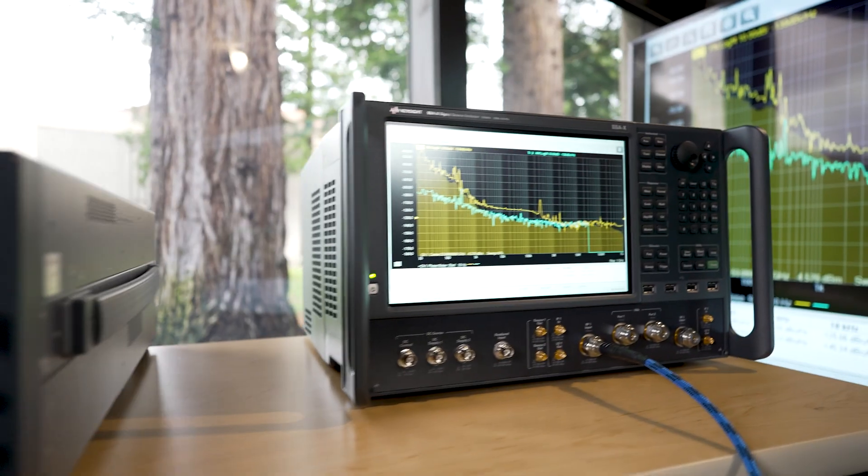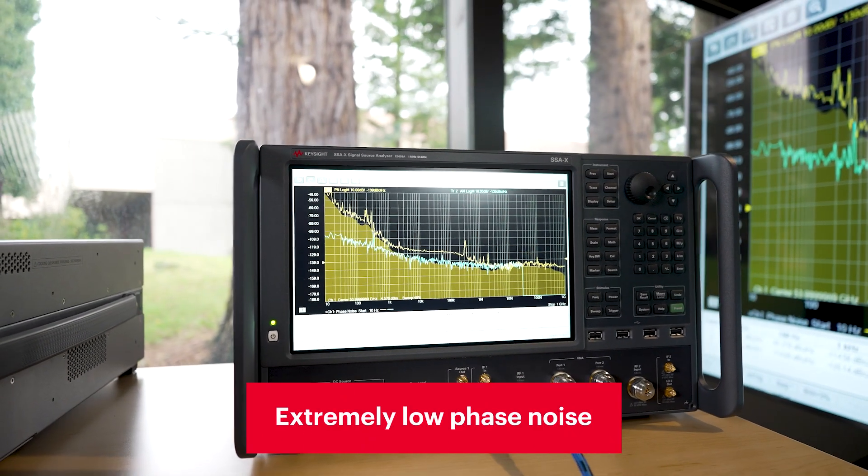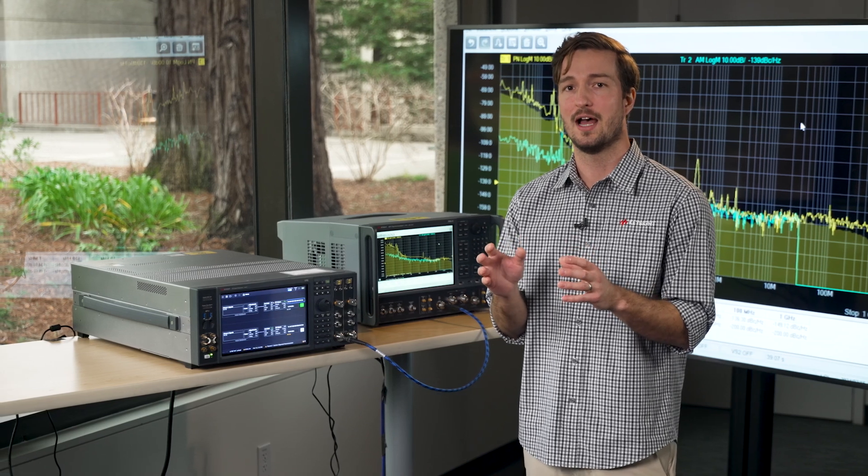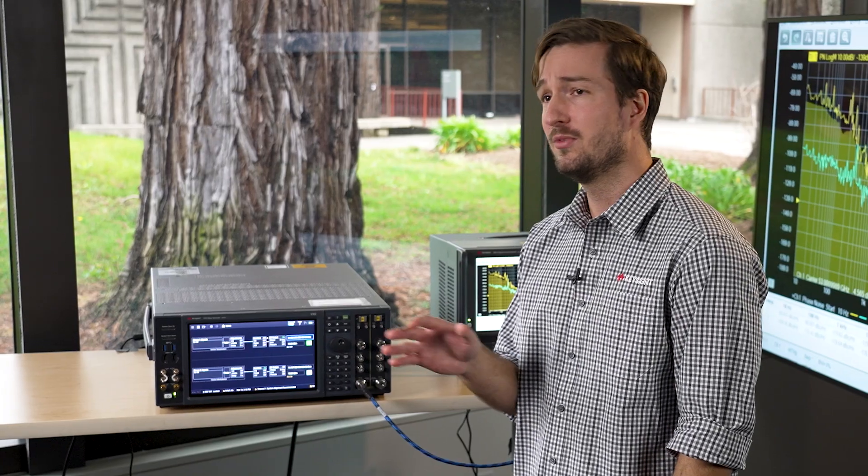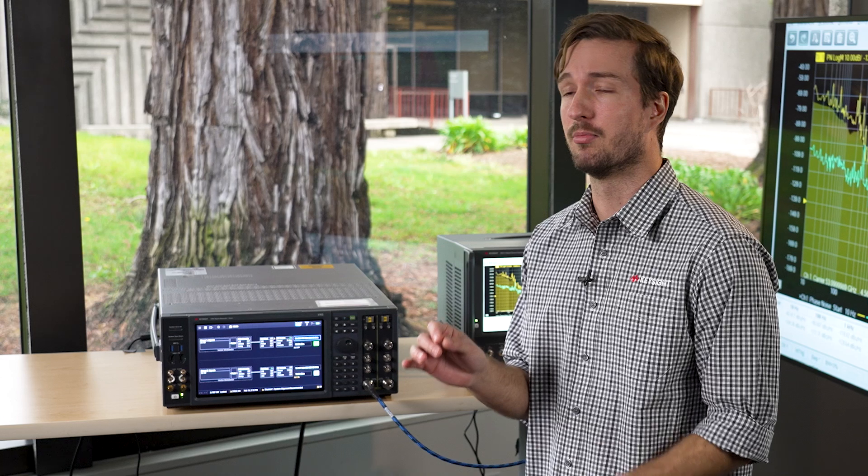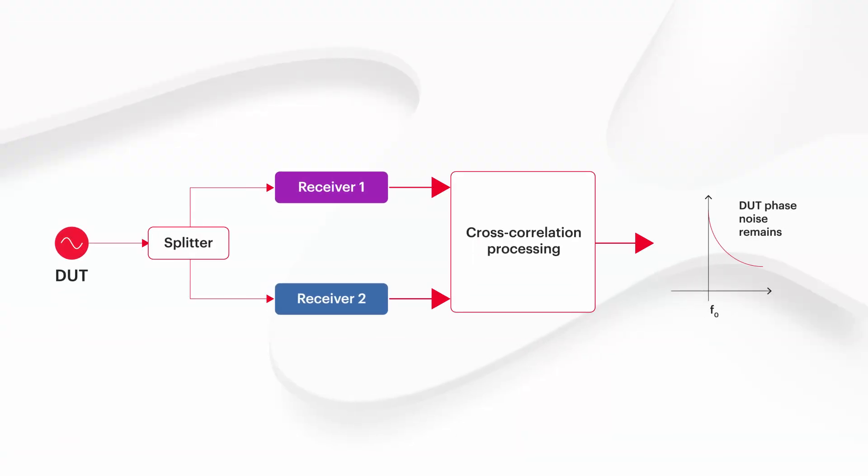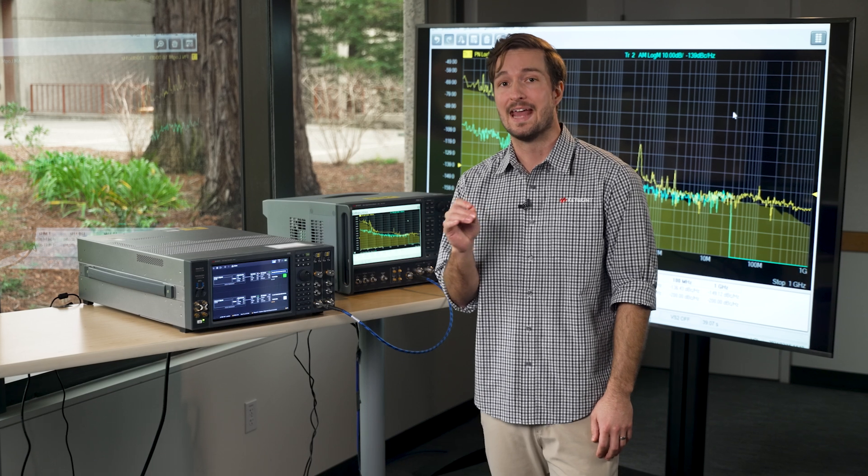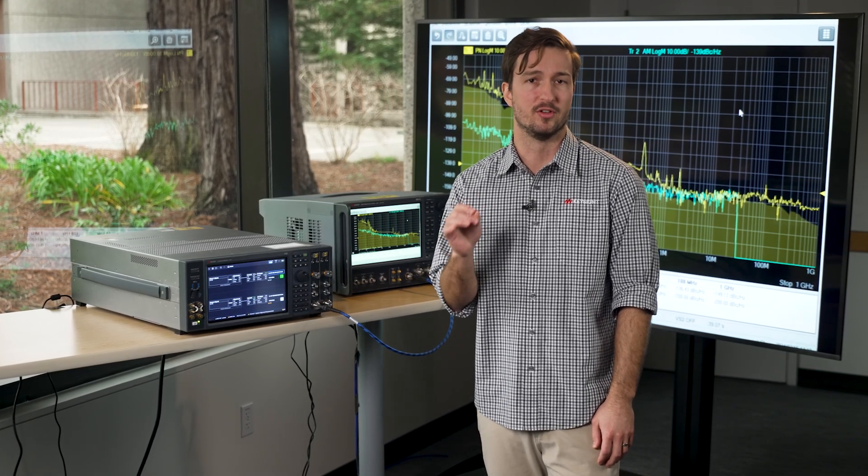The VXG has extremely low phase noise. In order to measure devices like the VXG, the SSA-X needs very high measurement sensitivity. This measurement sensitivity is achieved using a process called cross-correlation, where uncorrelated noise from two independent LOs and receivers is removed and the correlated noise from the DUT that is common to both receiver paths is retained. This removes the instrument noise from the measurement and allows sensitivity down to the KT thermal noise floor.